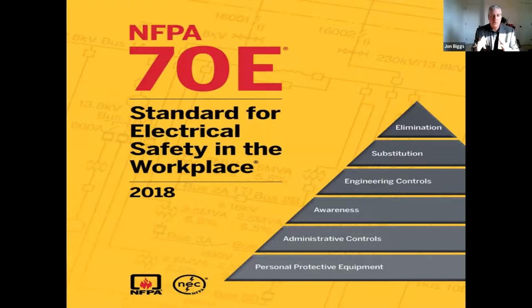That remains the intent moving into 2021, and likely will continue moving forward. In NFPA 70E, the goal is to eliminate electrical hazards—shock, arc flash, and arc blast—if at all possible. But if we can't, and there are times we can't, such as needing to test or troubleshoot equipment with electrical energy present, we need to minimize the hazards as much as possible using some combination of substitution, engineering controls, awareness, and administrative controls. Personal protective equipment should be viewed as the last measure of protection. How can we combine these five things if we can't eliminate the hazard, to minimize it as much as possible?